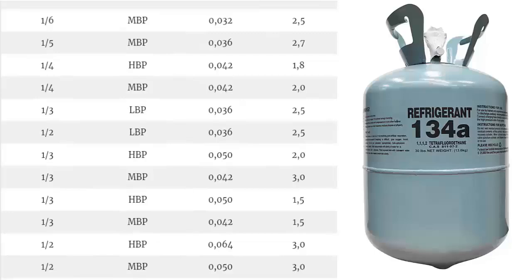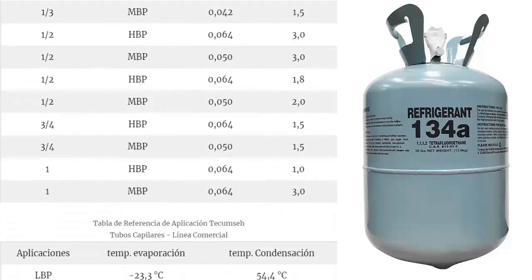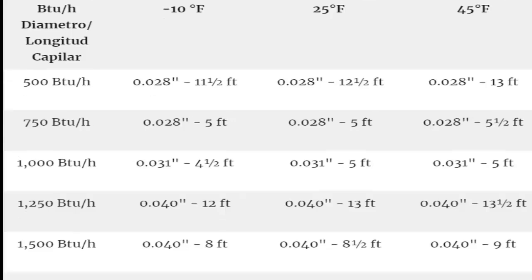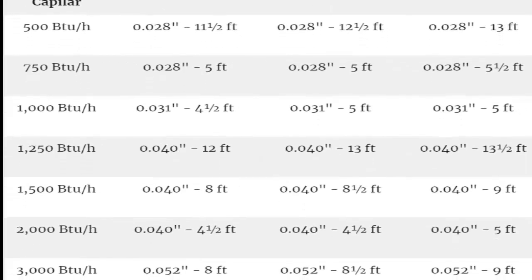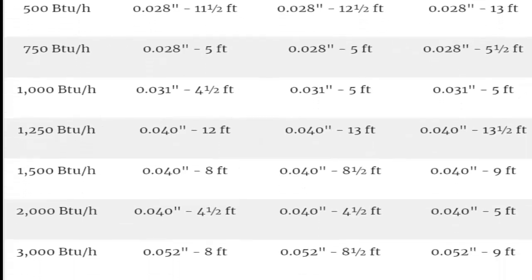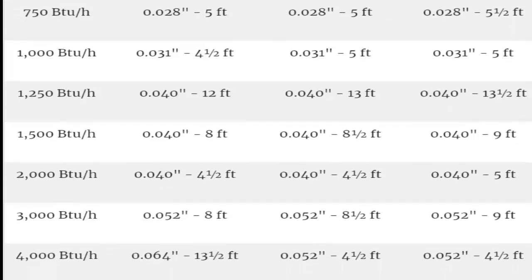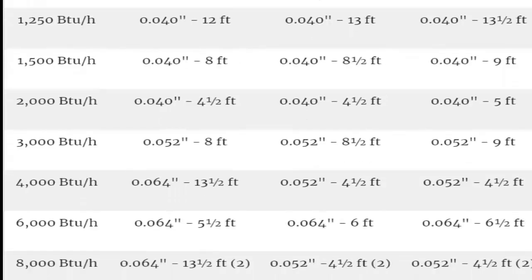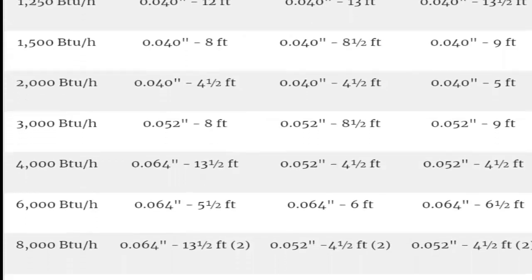B. Although tables based on electrical power in HP exist, it is more advisable to use tables based on cooling capacity in kilocalories per hour, BTUs per hour, or watts. C. For the same electrical power value, different models of compressors may yield different cooling capacities.